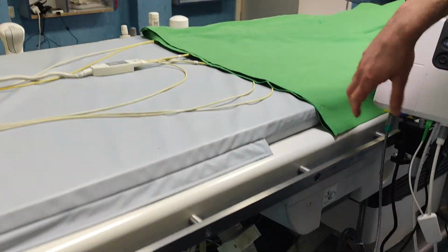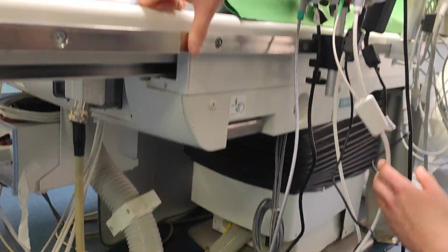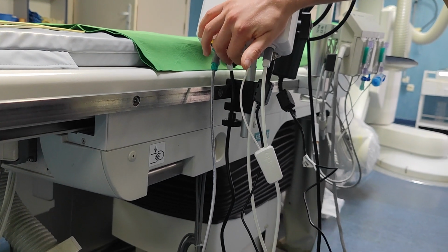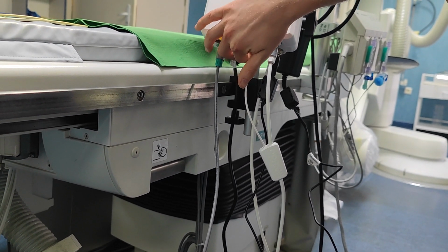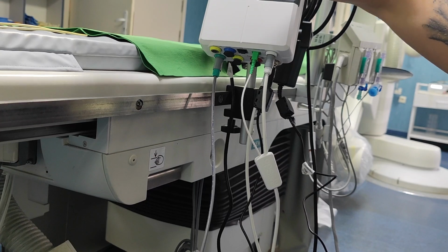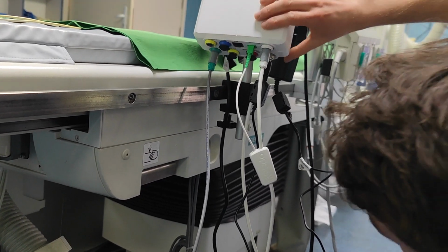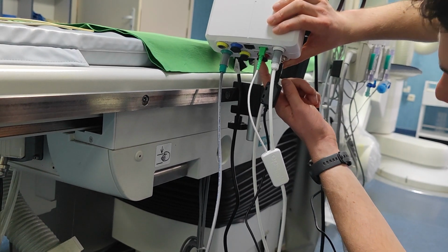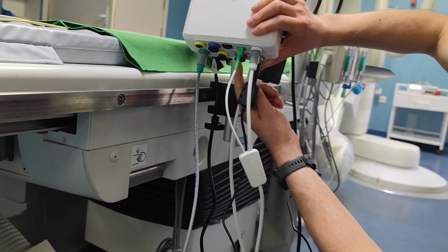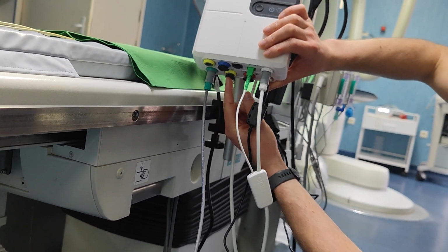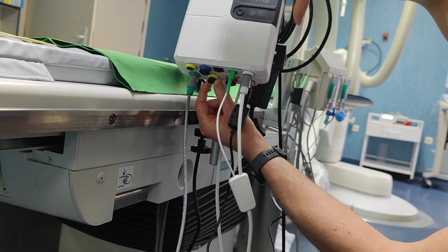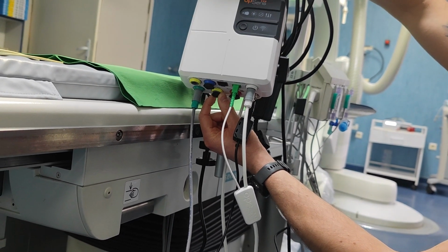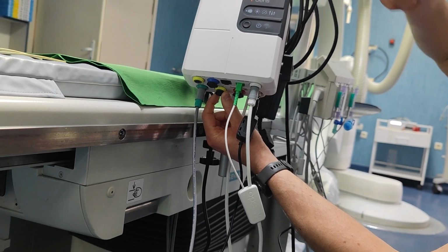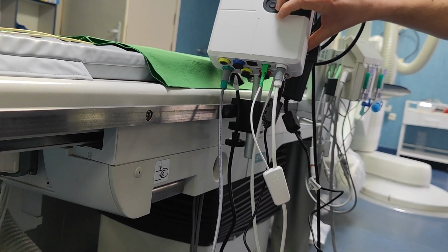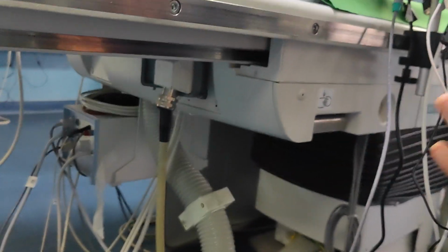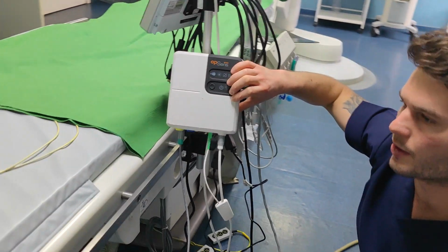So you plug this wire? So if you're using the transducer setup, you will have two cables. One coming from the transducer, which goes into our aortic in or aortic transducer, and then the output cable, which sends the aortic signal from the transducer, with the signal from the distal from the wire itself, out into their hemodynamic system. So it depends. There's two different setups you can use, depending on the lab, depending on how you use it.